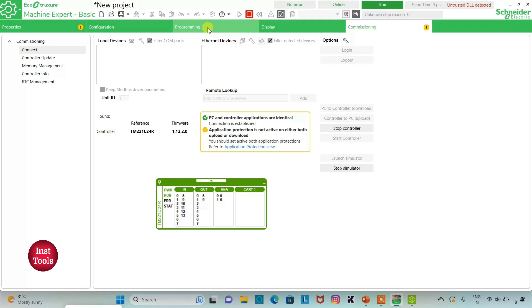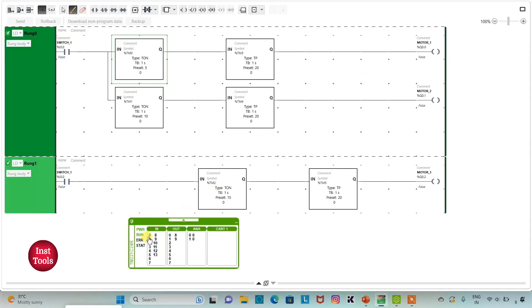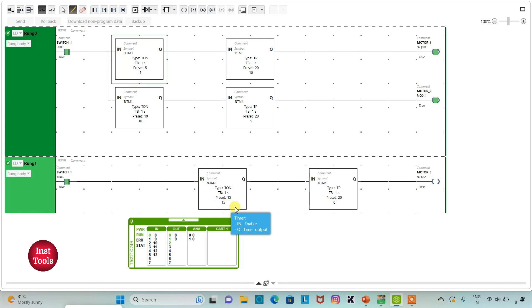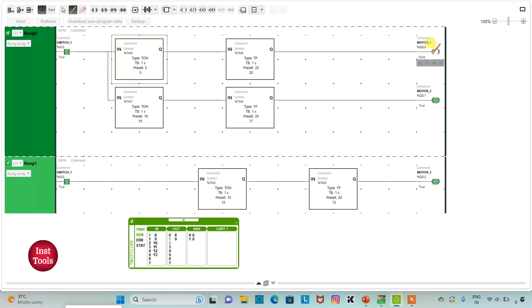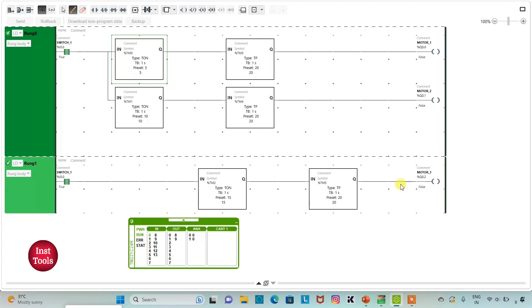I will go to programming and click on full screen mode. When I turn on Switch 1 — that is I0.0 — counting: 1, 2, 3, 4, 5 — and motor 1 will be on. Then 7, 8, 9, 10 — after 10 seconds motor 2 will be on. And 11, 12, 13, 14, 15 — motor 3 will be on. Then 16, 17, 18, 19, 20 — and after 20 seconds motor 3 will be off and all motors will be off.